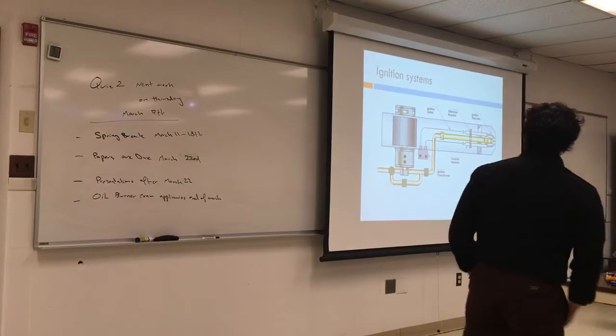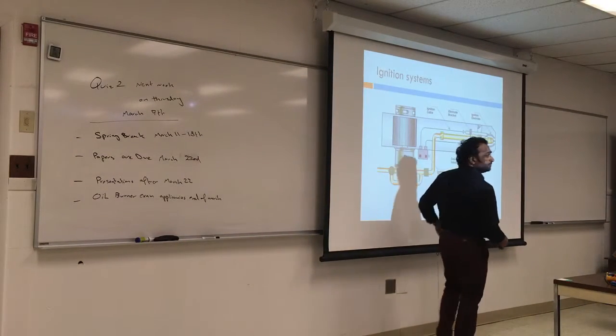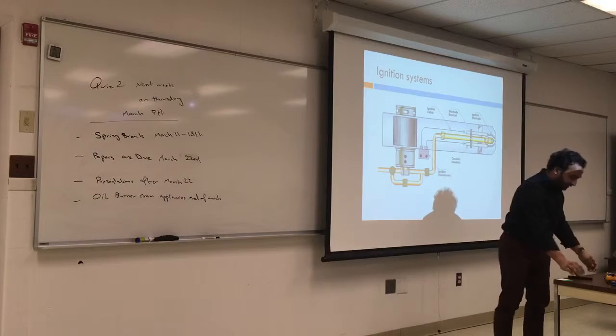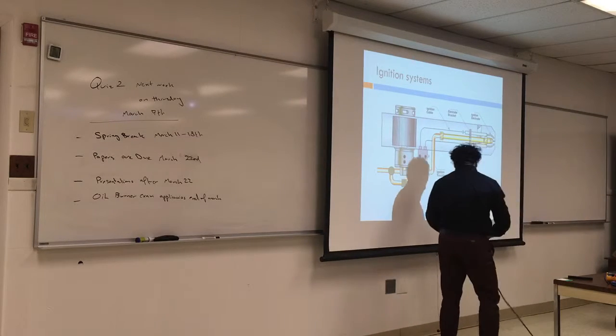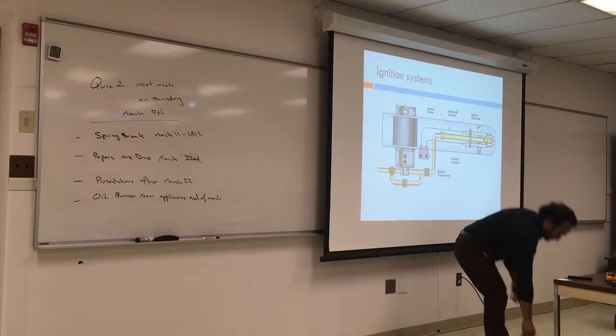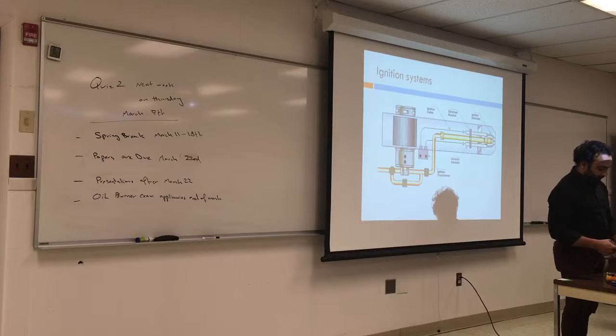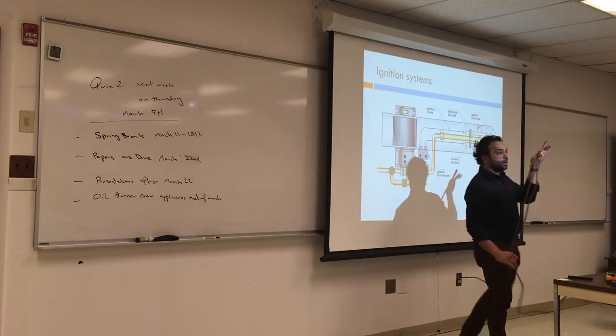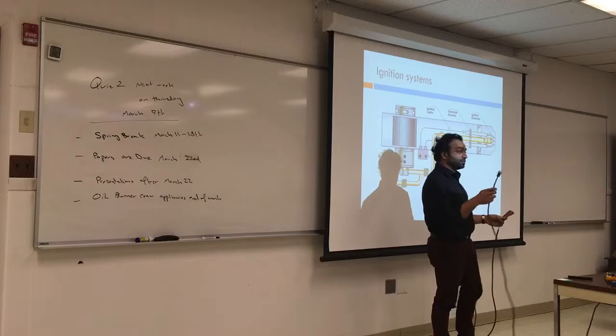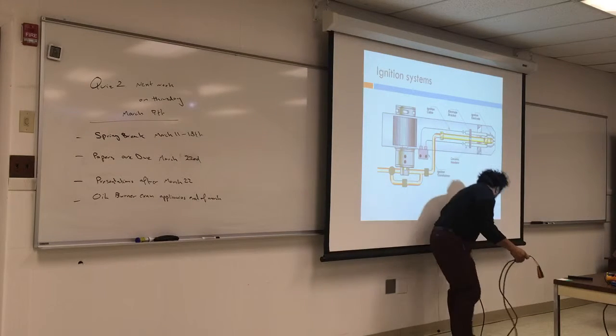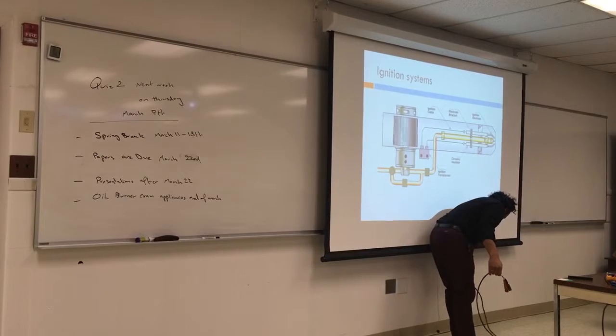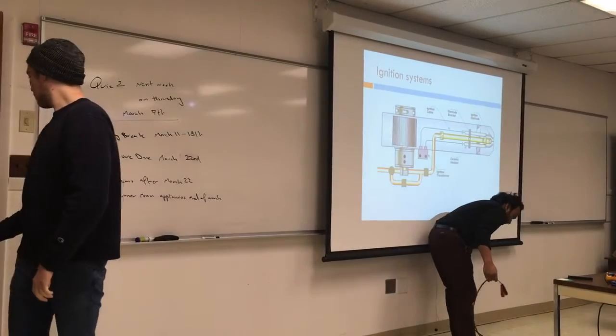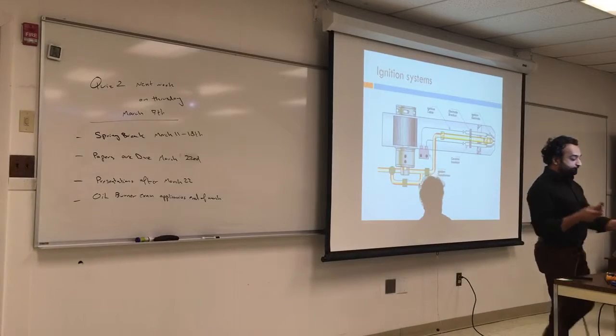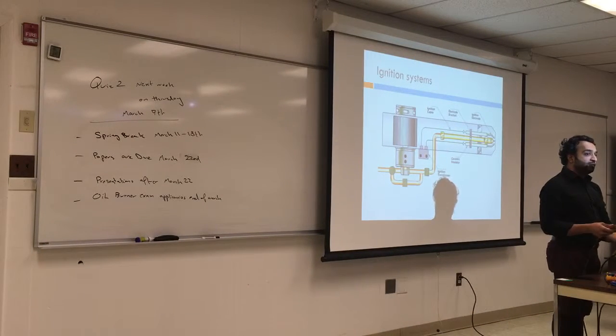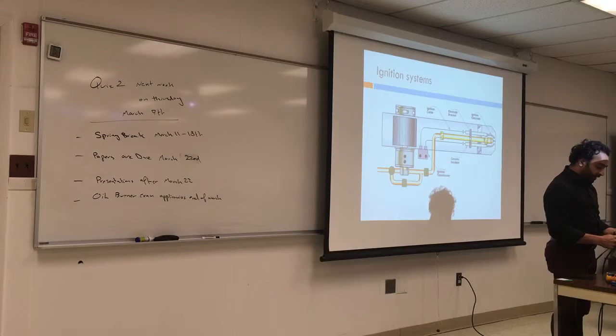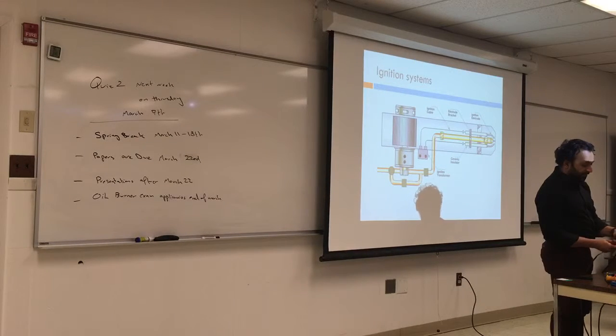So ignition system, we've seen these before. What is the purpose of the igniters here? They produce a spark. Actually, luckily I have an igniter here. We've seen it before. So you always want to go with the alligator clips because they enable you to plug in. So you can take out your igniter from the primary and you connect one to hot, one to neutral.